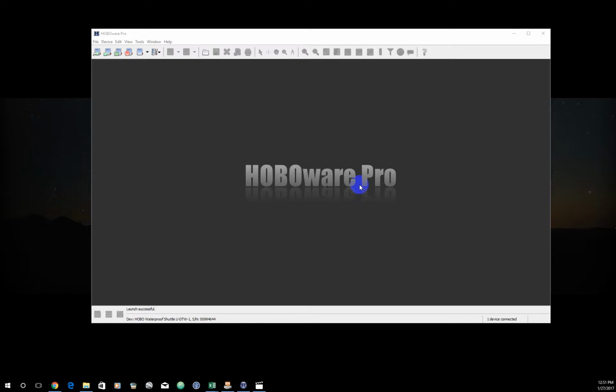So as before, in this case, you are going to need your field laptop with you when you go on site to get the data, to collect the data. You'll go in, open up your computer, go into HOBOware Pro, connect your shuttle, all similar to as you did when launching. It'll show you your shuttle is connected.